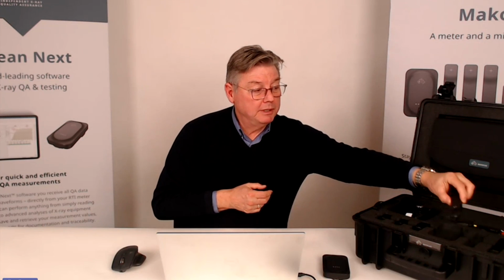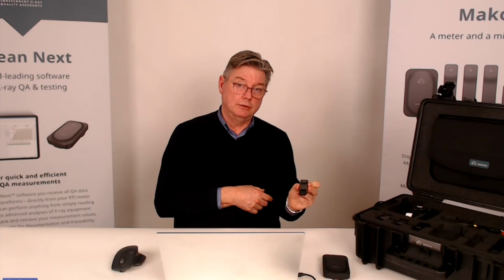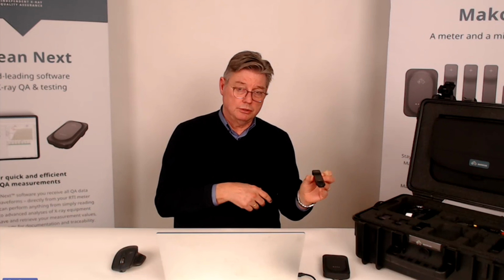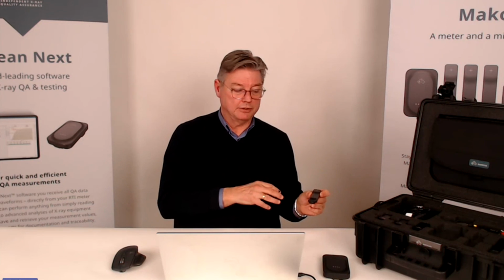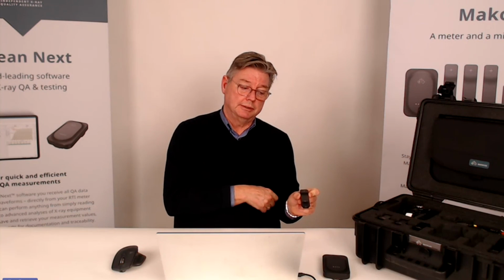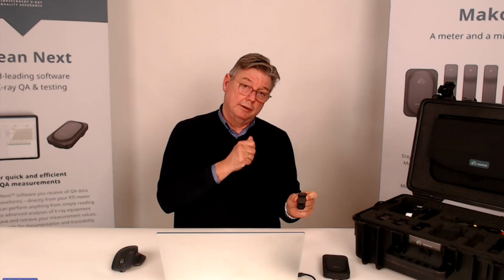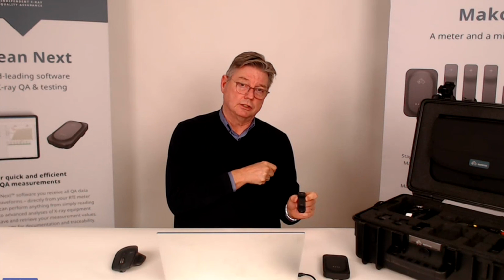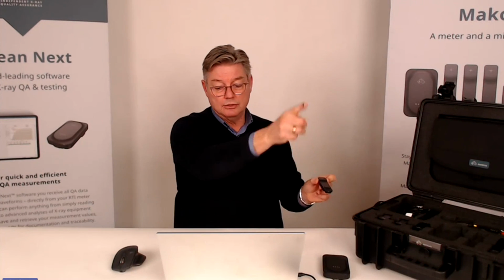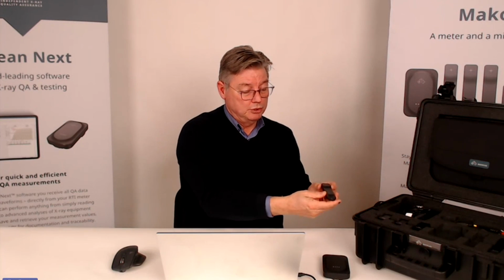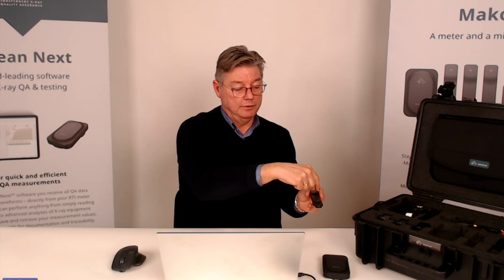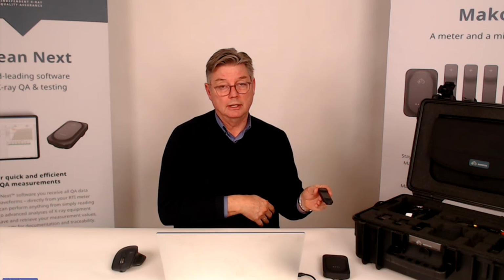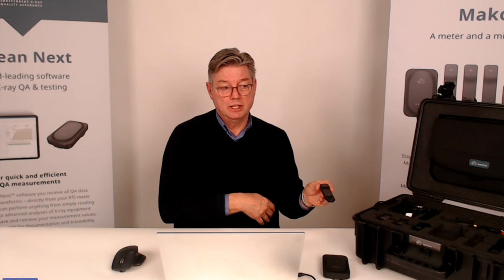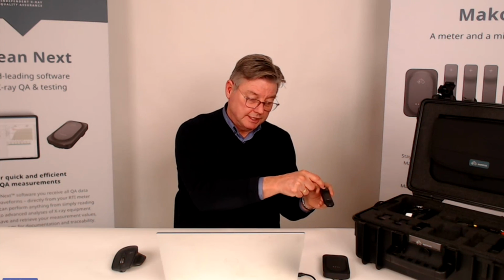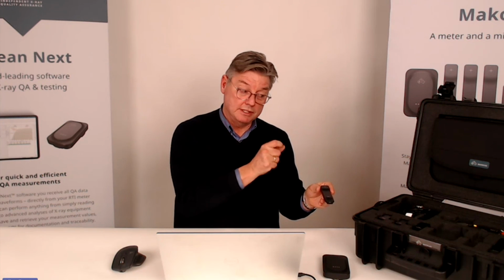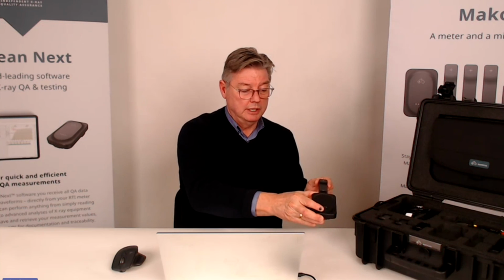Yeah, of course, for measuring on CT, you can have it on the table, on the couch, or at the bottom of the gantry. It doesn't really matter. What matters is that we need to have that detector in place. So the distance doesn't really matter for it. But what is good, if you remember, we talked about the segmented detector. If the gantry is like so and the couch is in this direction, we should put it like so, because then we have the possibility to see the balance using the segmented detector, the center detector, and to see the balance that we're actually hitting the beam with, if it's a narrow beam.